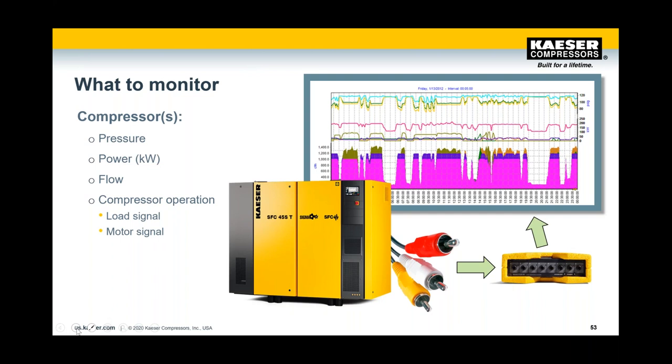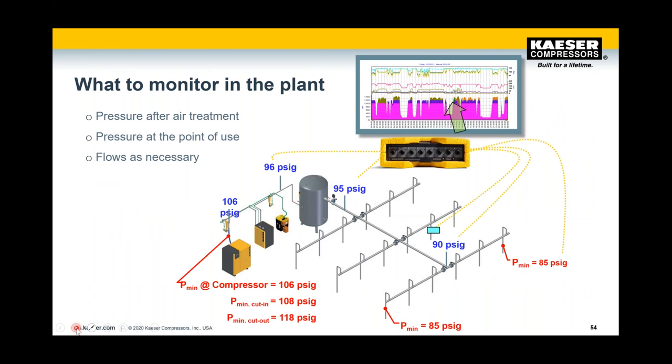What if you don't have the information available from your controller? Monitoring your existing station is a great way to start — track pressure, flow, and power for each compressor, as well as operational signals like load and motor status. However, that's just the supply side. To get a bigger picture of what's going on in your system, monitoring pressures and flows on the demand side will help you complete that puzzle. A simple example includes additional pressure measurements to create a pressure profile across your system, as well as a point-of-use flow meter.